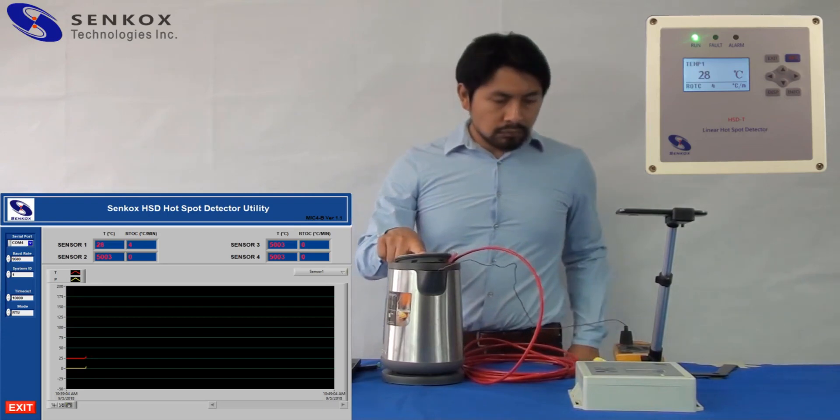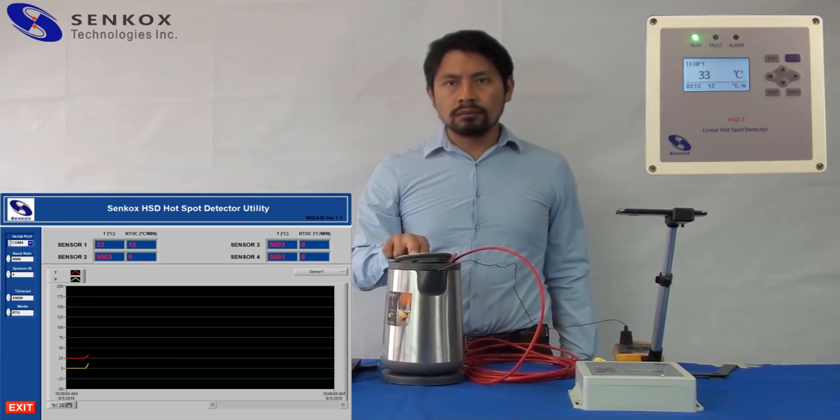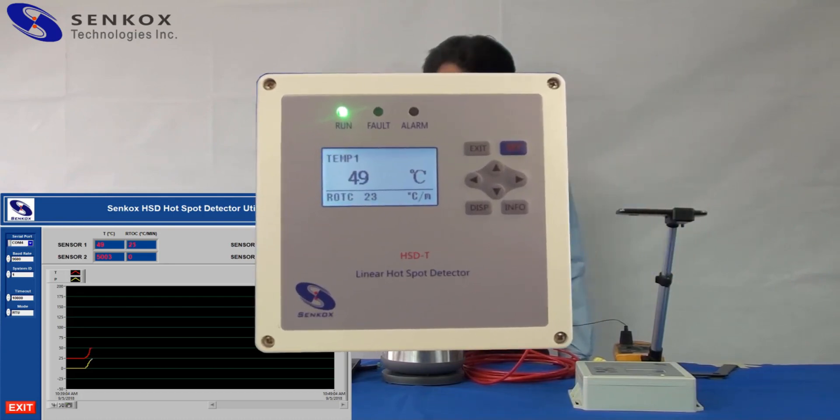You can set the alarm temperature at any value from negative 40 to 260 degrees Celsius. Now you can see on the HSD module that the alarm got triggered because the temperature is above 60 degrees Celsius, also indicated by the red LED light.